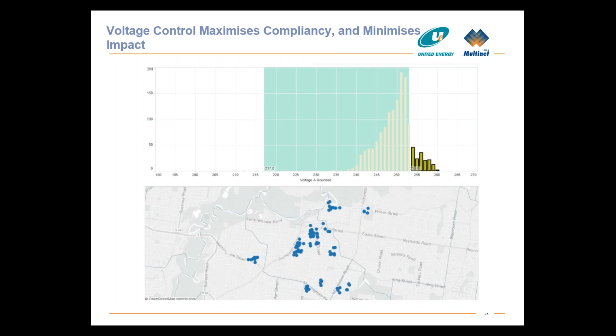One of our big successes is the work we've done detecting neutral issues on customer premises. This is a typical household: our transformer is earthed, and the house is also earthed, with a live and a neutral coming to the house. The big problem is the moment something goes wrong with the neutral, we sit with a good live to the house, and current goes back through earth that is high resistance, so we start to get reasonably high voltages at customers' premises that can cause shocks.